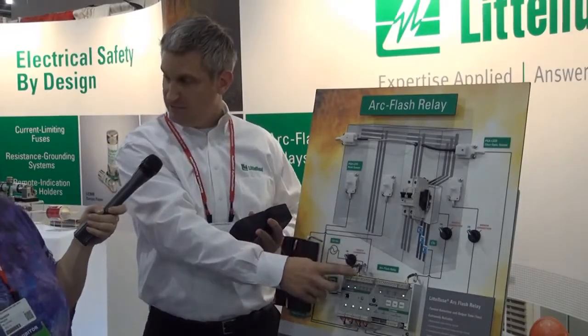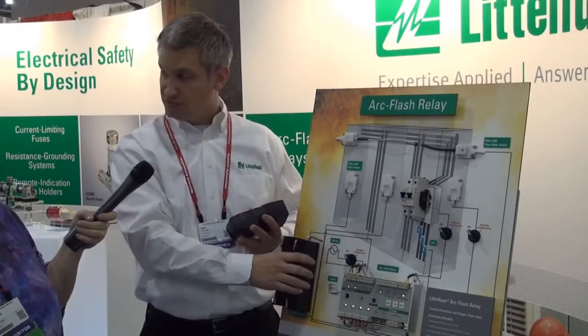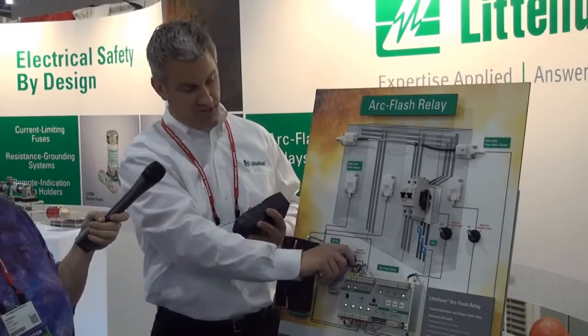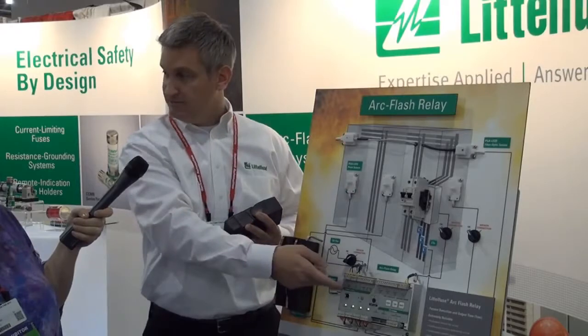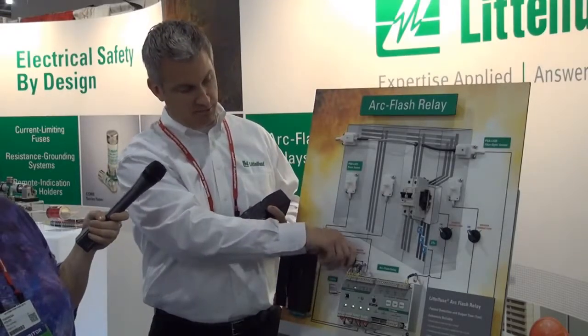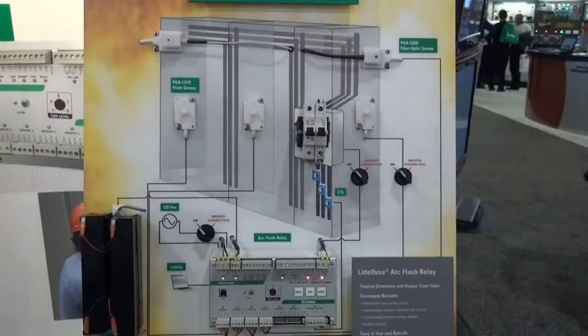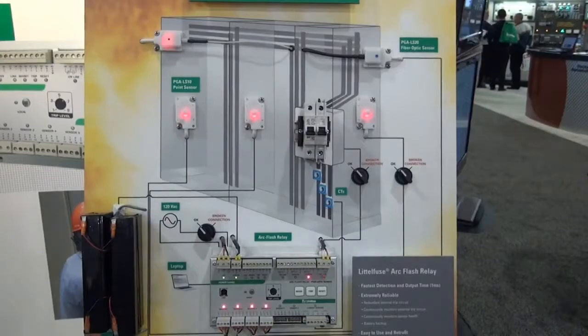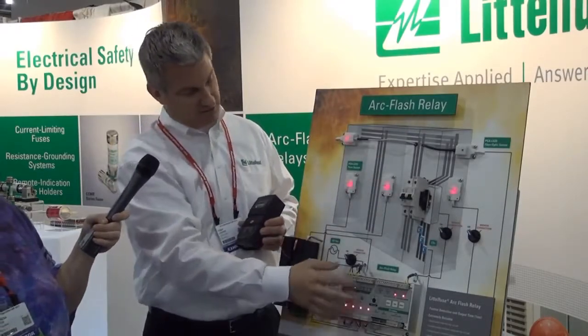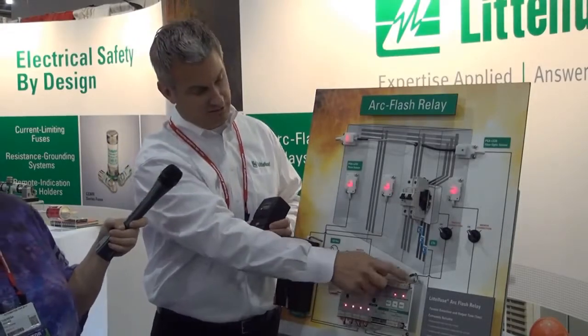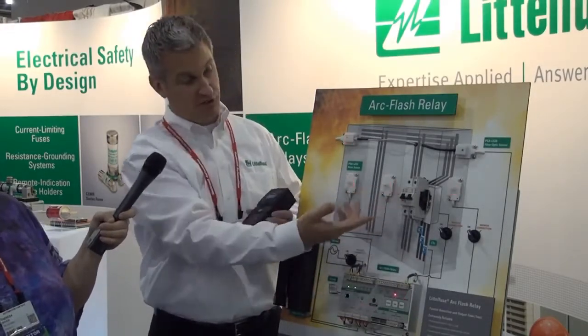Give me a second here for this flash to charge up. It also takes control power coming into it. It actually recharges a rechargeable battery to normal operation. So if you were to lose power, it now gets its power from the batteries. So again, another reliability feature there. And now I'll demonstrate, so this will simulate an arc flash incident here. As you can see here, it saw the light. All four sensors, 1, 2, 3, and 4, saw the light. The signal went into the relay, it saw the condition, and it sent an output up to the circuit breaker, and you can see it trip now.